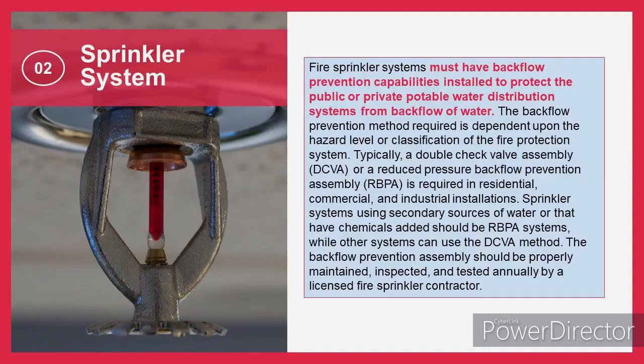Fire sprinkler systems must also have backflow prevention capabilities installed to protect the public or private potable water distribution systems from backflow of water. The backflow prevention method required is dependent upon the hazard level or classification of the fire protection system. Typically, a double check valve assembly, DCVA, or a reduced pressure backflow prevention assembly, RBPA, is required in residential, commercial, and industrial installations. Sprinkler systems using secondary sources of water or that have chemicals added should be RBPA systems, while other systems can use the DCVA method. The backflow prevention assembly should be properly maintained, inspected, and tested annually by a licensed fire sprinkler contractor.